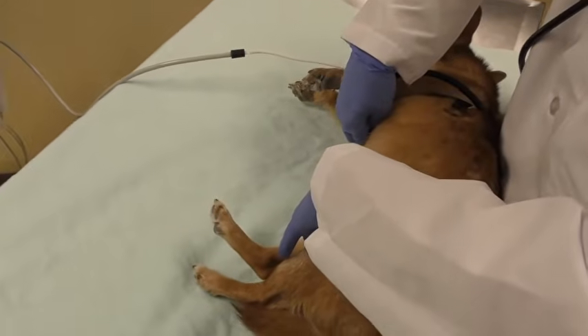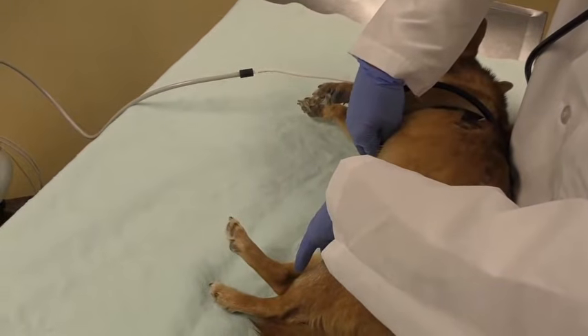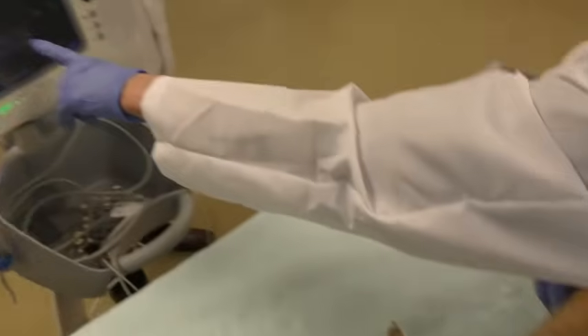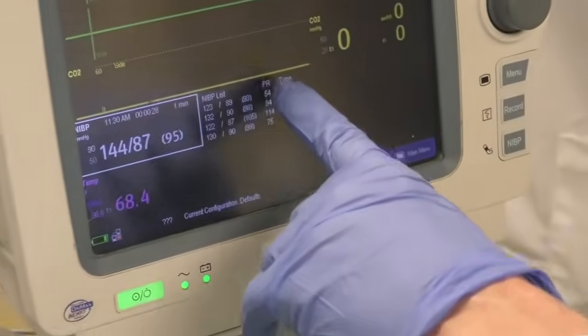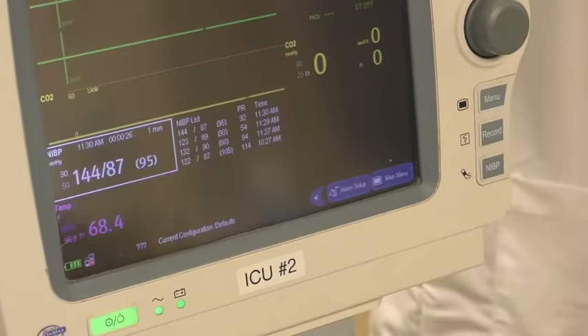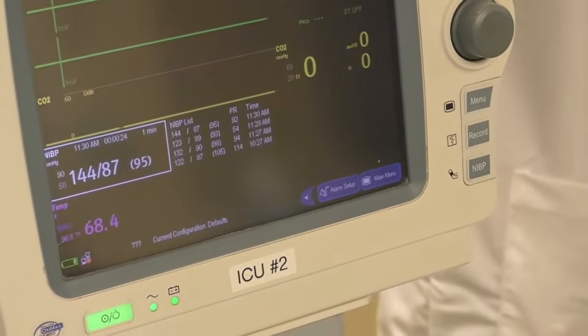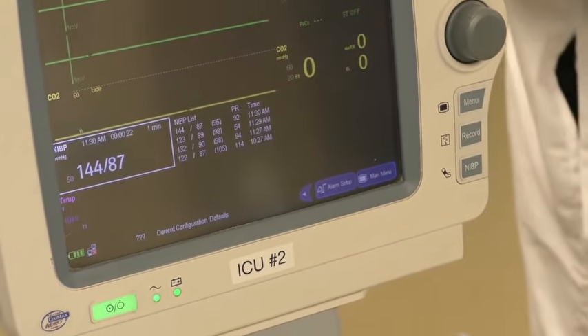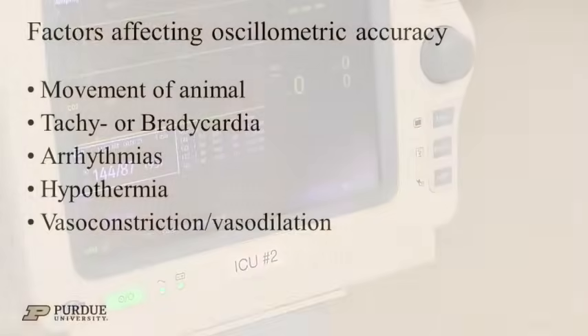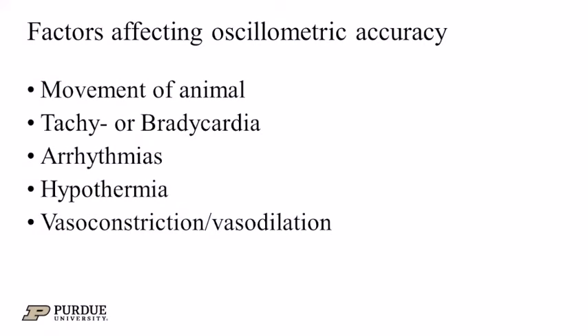providing continuous readings. Because oscillations in the blood vessel wall are caused by blood moving after the heartbeats, the oscillometric unit will report a pulse rate. Always compare the pulse rate to the animal's heart rate. If the heart rate does not match the oscillometric unit's pulse rate, the blood pressure cannot be trusted. Factors that affect the accuracy of oscillometric include the movement of the animal, significant tachycardia, bradycardia or arrhythmia, hypothermia, and vasoconstriction or vasodilation of the peripheral vessels.